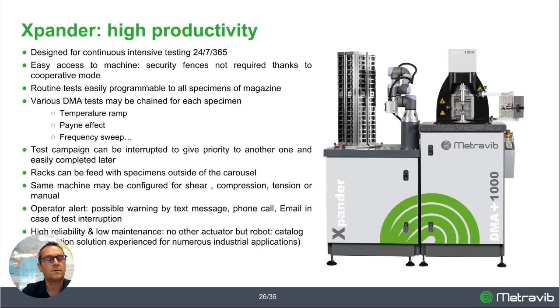The racks storing the specimen can be fed with a specimen outside of the carousel to avoid losing some testing time. The same machine can be configured for shear, compression, and tension in automated mode or in manual mode. We also have a function called operator alert that makes it possible to warn the operator by a text message, phone call, or email in case the test is finished or interrupted, and that avoids losing too much time without testing.